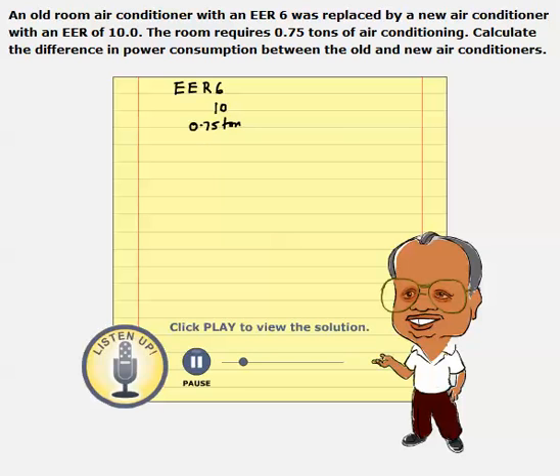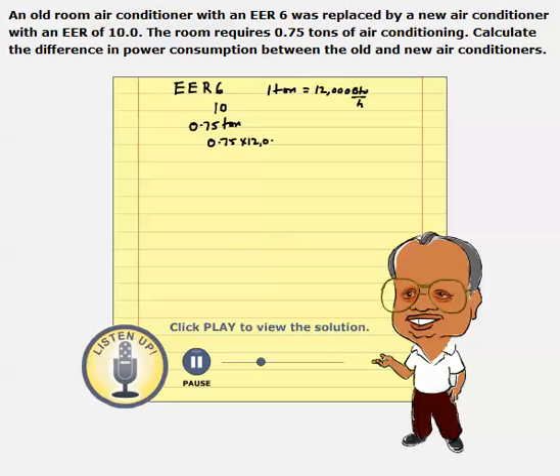You should remember that each ton — one ton of refrigeration or air conditioning — is equal to pulling out 12,000 BTUs every hour. So it is pulling out three quarters of a ton, which is 0.75 times 12,000 BTUs per hour. That is 9,000 BTUs per hour.